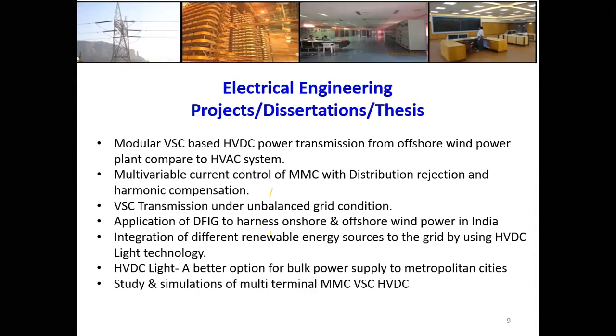Also, we know there is one technology that is current source converter based and one technology that is voltage source converter based in HVDC. So you can study - take the case of Padghe 400 kV. At Padghe 400 kV, the HVDC, that is conventional HVDC based on thyristor, is already connected to that bus.